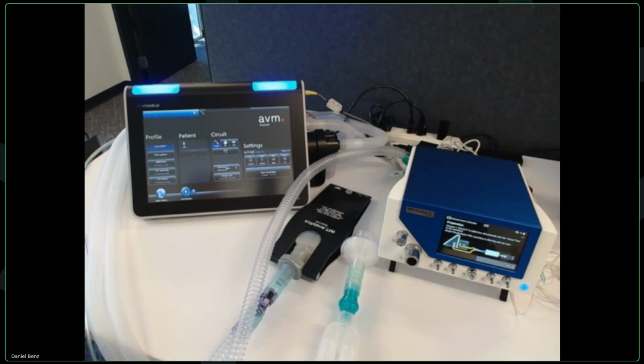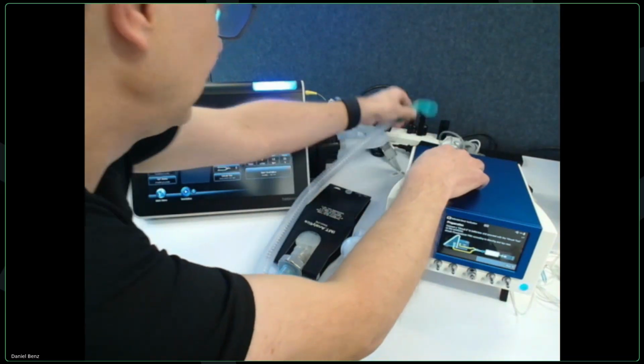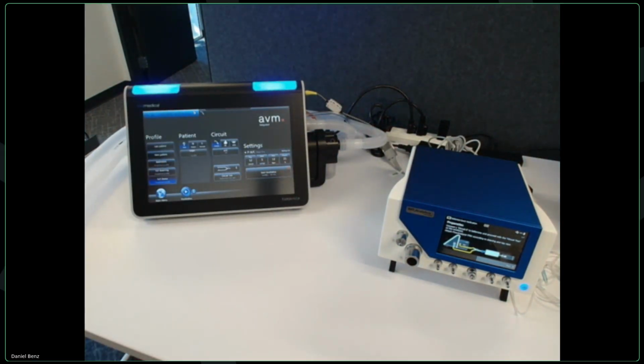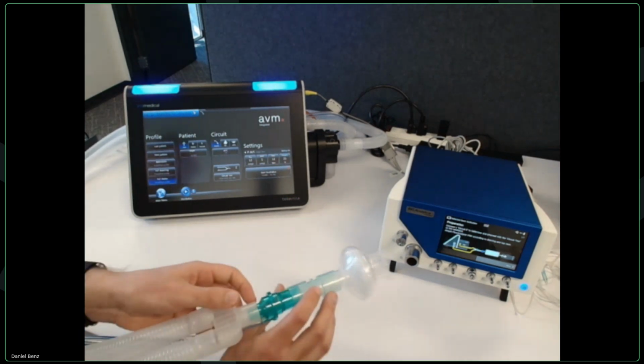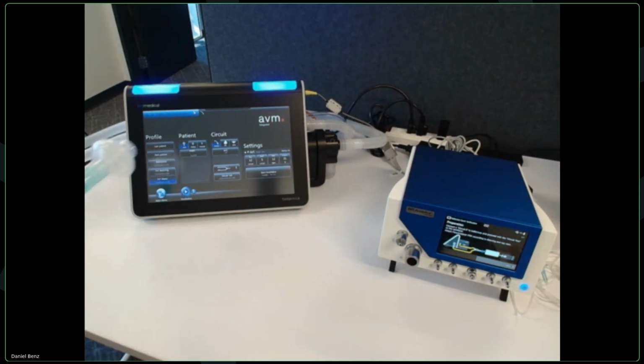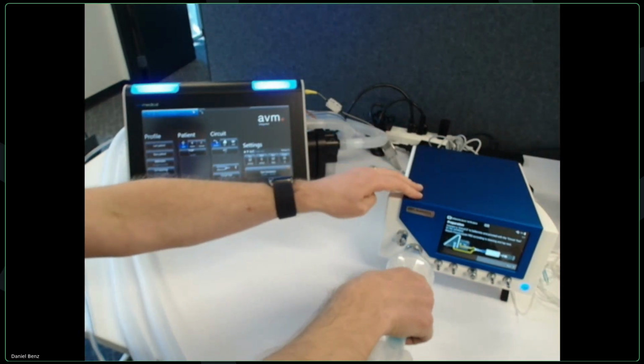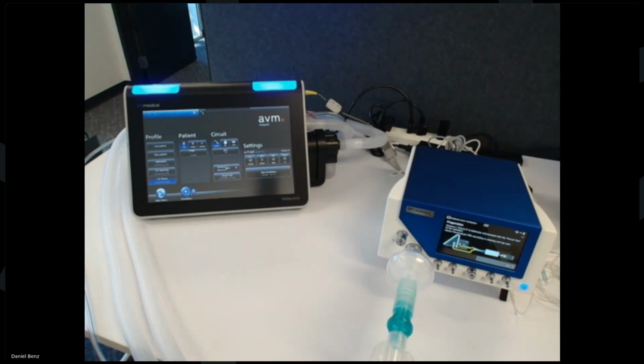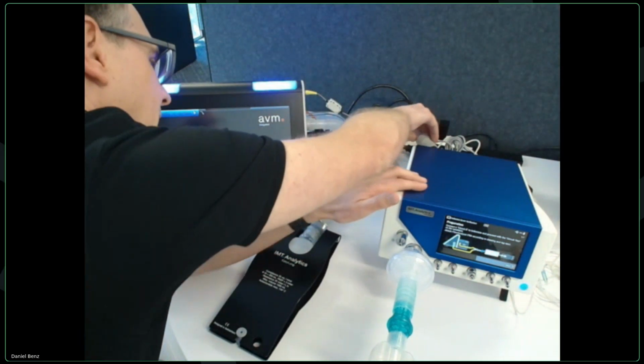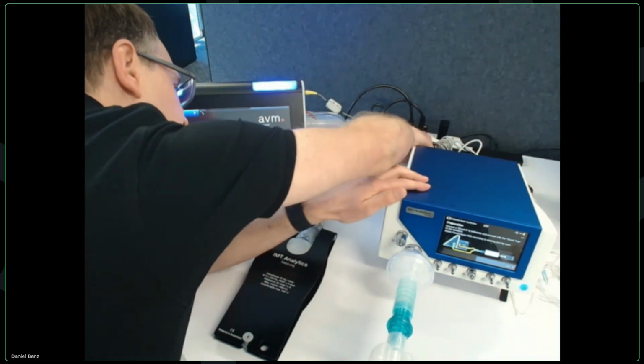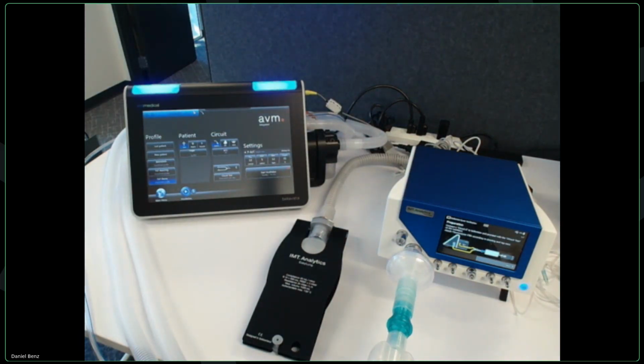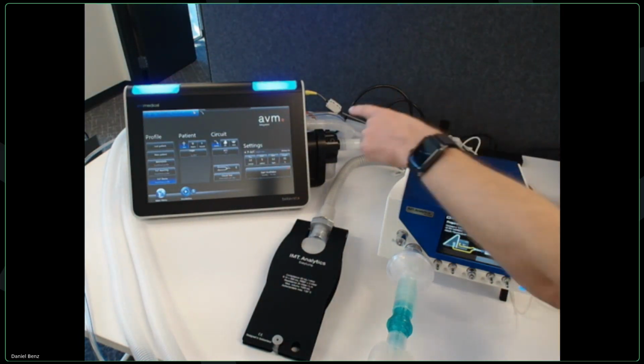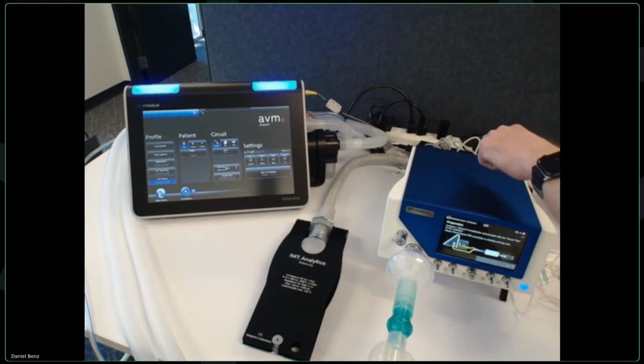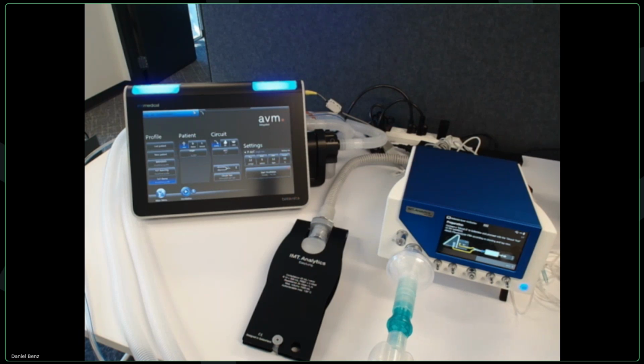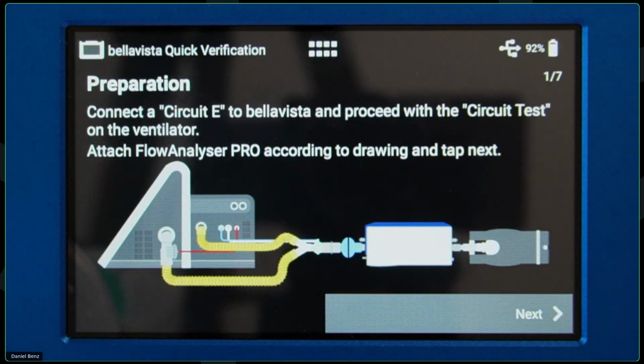So let me make that setup a little quick. I'm gonna show you that on the camera as well. So I'm gonna disconnect this CPAP circuit system here and bring back my test lung. And first of all, I'm gonna connect the ventilator again to my main flow channel and my test lung to the back. So this is actually what I saw in the testing app for my setup. We have the ventilator circuit system through our flow analyzer and then to the test lung. You can see that in the app. So it shows you how to set it up.